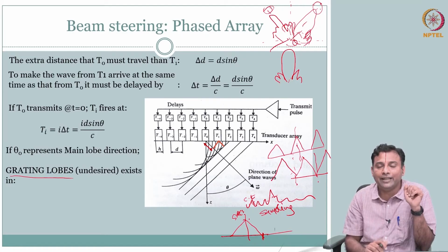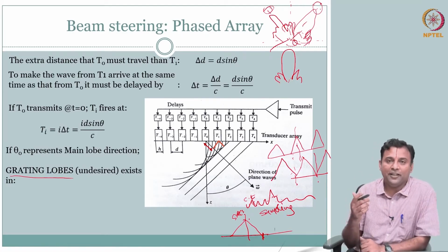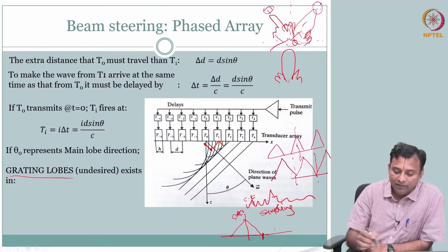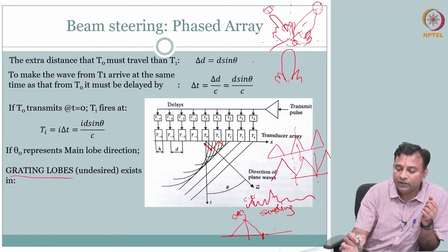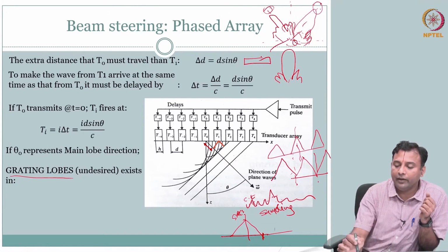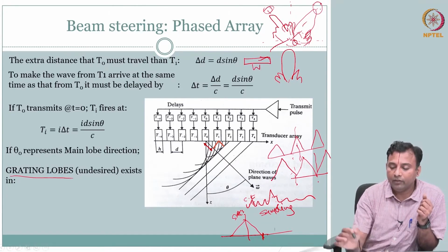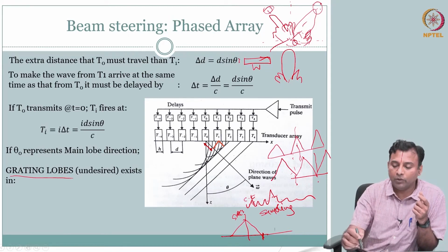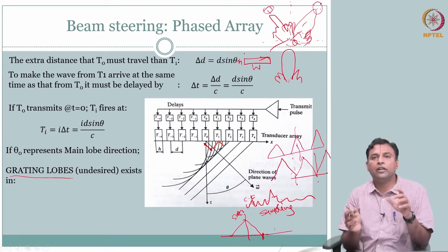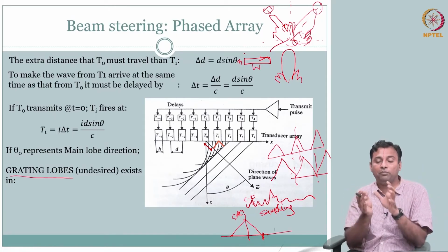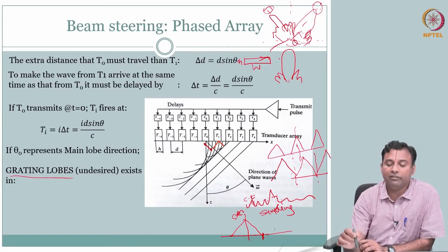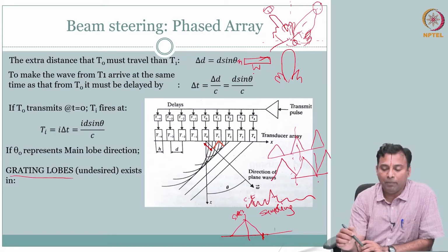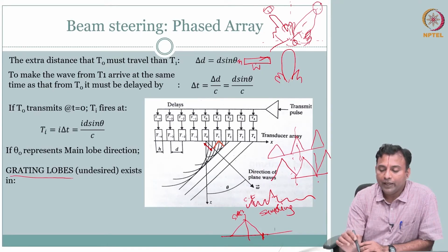However, here what are we sampling, right? In imaging it is all about space. Now, imagine what we covered so far for the main lobe and side lobe is just one transducer, right. We had a width, and let us not worry about elevation. So there was some height, but do not worry. If you look at the rectangular transducer for which we put the beam pattern, let us just take the width, which is in our imaging plane. You take this width. So this is your element that we had before.